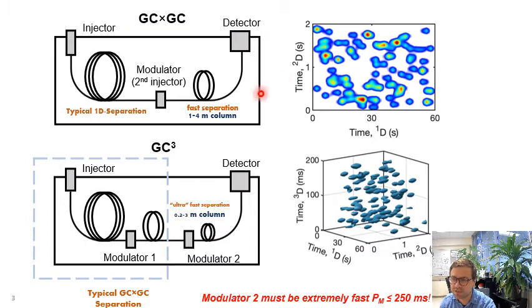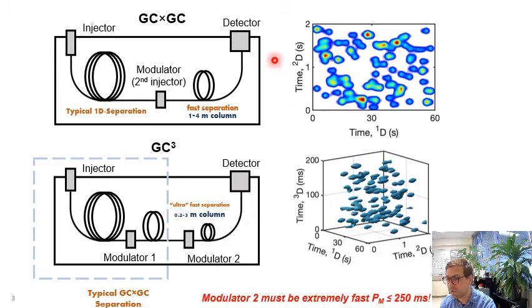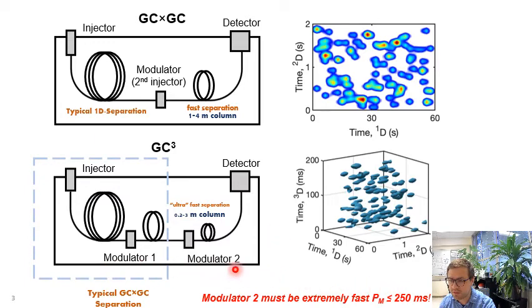Instrumentally, GC Cubed can be thought of as an extension to an existing GC×GC platform, consisting simply of an additional modulator and an additional short separation column. Since GC×GC peaks on the second dimension are on the order of a few hundred milliseconds, the second modulator in a GC Cubed instrument needs to operate at an ultrafast modulation period of roughly 250 milliseconds or less. The resulting data, which is reshaped, can be viewed in its natural 3D dimensionality as an isosurface chromatogram, as shown here.